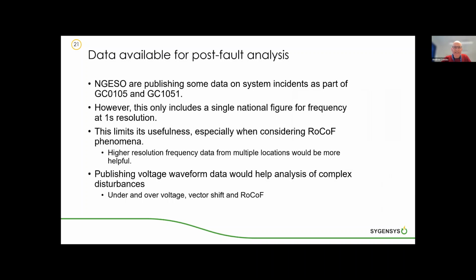Another area we considered, and this is a bit of a request to National Grid ESO. They are publishing some really helpful data on system incidents as part of the GC105 and 151 provisions. However, this only includes a single national figure for frequency at 1 second resolution. And this does limit its usefulness, especially when you're looking at RoCoF phenomena. So higher resolution frequency data from multiple locations would be more helpful. And in addition to that, publishing waveform data from system incidents would help with the analysis of complex disturbances. Particularly now we're trying to look at under-voltage tripping, vector shift behavior, which we'll consider next, and RoCoF effects.